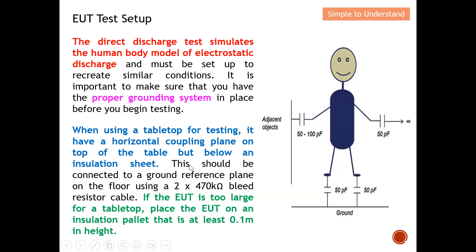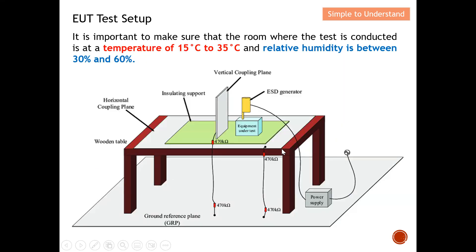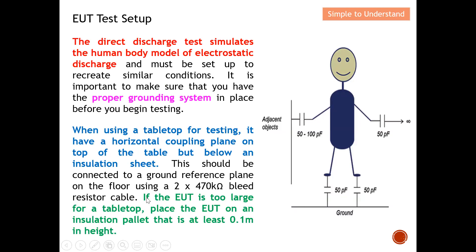The horizontal coupling plane should be connected to a ground reference plane on the floor using two 470 kΩ bleed resistor cables, as illustrated. If your EUT is too large to place on a table, you need to place it on an insulation pallet that is at least 0.1 meter in height before performing the test.